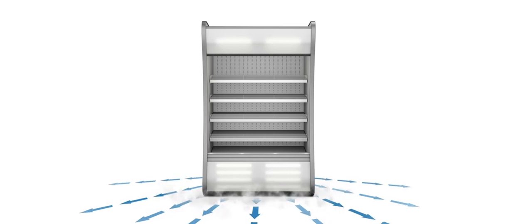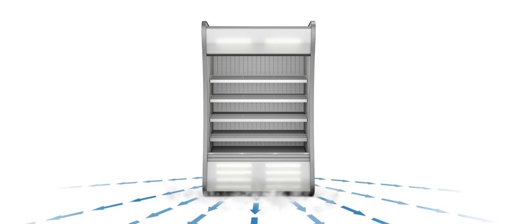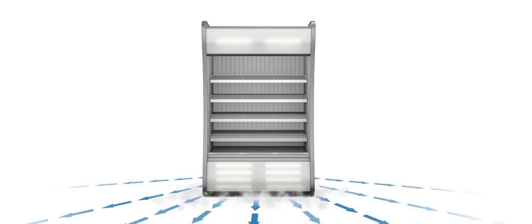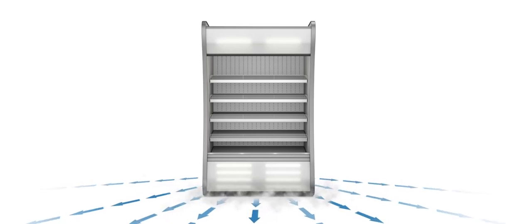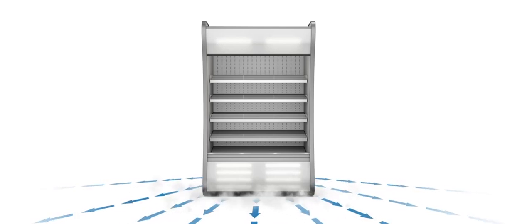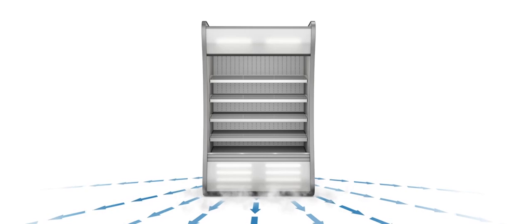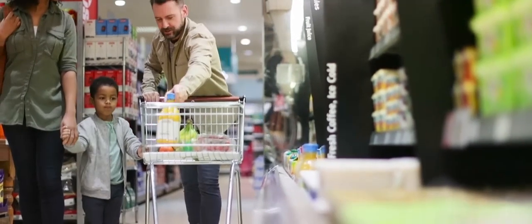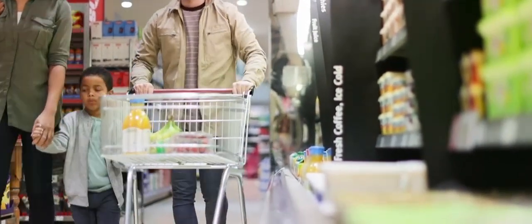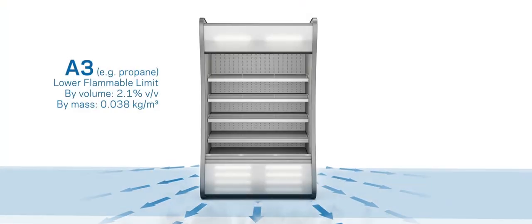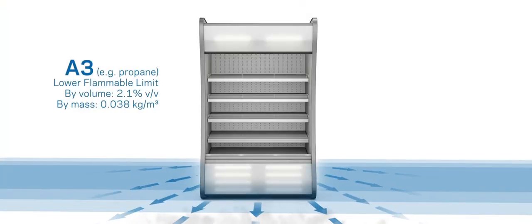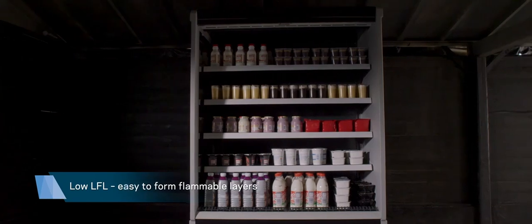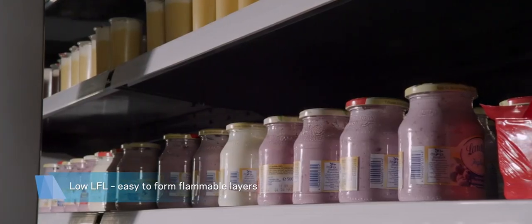So if during a leak situation, the leak rate and the quantity released is large enough that it surpasses the lower flammability limit, flammable concentrations can form. Propane is a commonly used low GWP refrigerant in small refrigerated cabinets, but its lower flammability limit is only 2% propane by volume in air. This means that for even small charge sizes, flammable layers can form and actually ignite and burn.